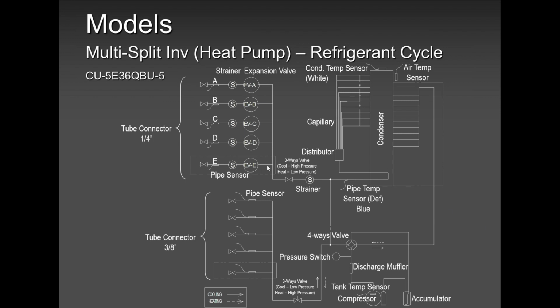Electronic expansion valves, when these units are not calling for heat, any one of them, they will close, but they will be slightly open. There will be a slight allowance for oil return. So keep in mind, they are never fully closed. When other zones are running, the zones that are not running are still allowing a slight amount of refrigerant to go through, because we want oil back. We don't want oil to get trapped at the indoor unit or somewhere in between. We want that oil to come back into this compressor here.